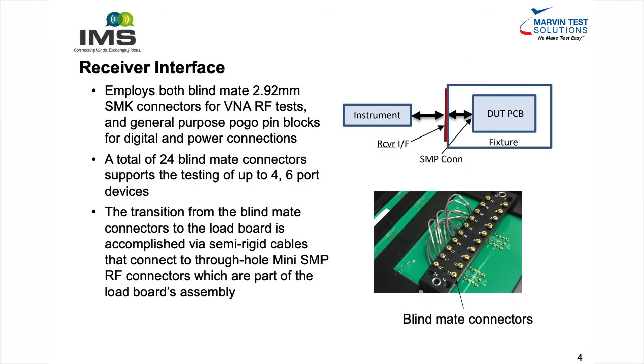The receiver interface implementation supports the delivery of 24 VNA RF signals via 2.92 mm SMK blind mate connectors to a device load board. General-purpose POGO pin blocks provide for digital control signals and DUT power. The transition from the blind mate connectors to the load board is accomplished via semi-rigid cables that connect the SMK mating connectors to through-hole mini SMP RF connectors, which are part of the load board's assembly.